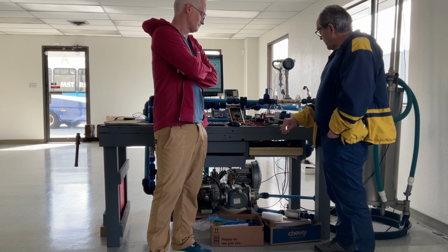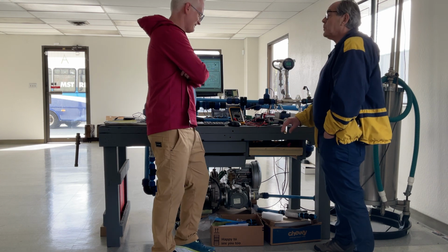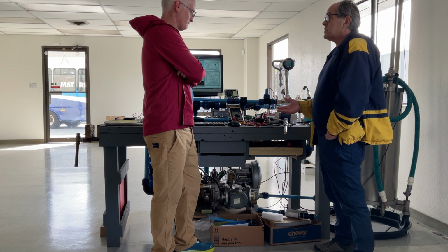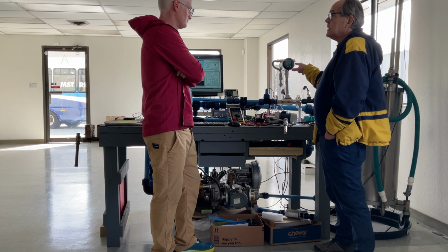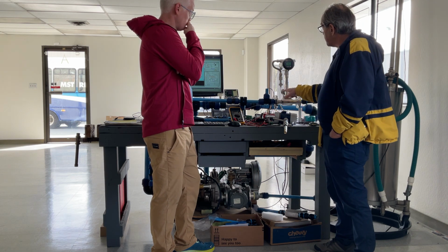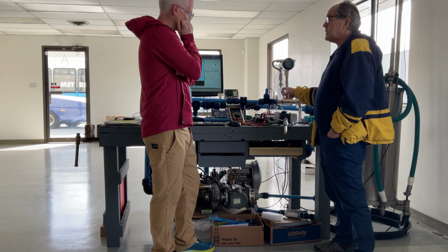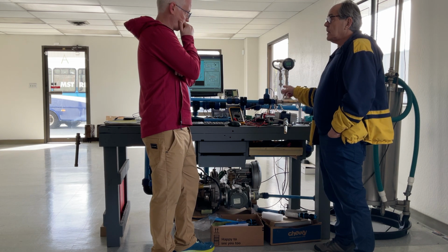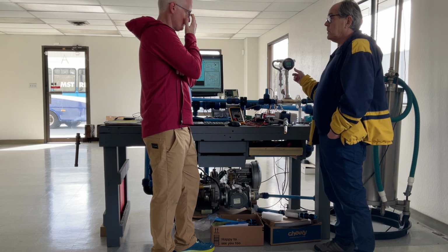The folks who make these, I know because I do consulting with them, don't really do it the perfect way, let's just say, but it's good enough. This one doesn't care. This one doesn't care about the composition. Vortex just looks at that. This one also has a pressure transducer and a temperature transducer, so it's a multivariable flow meter. It can indicate in volume or mass flow.